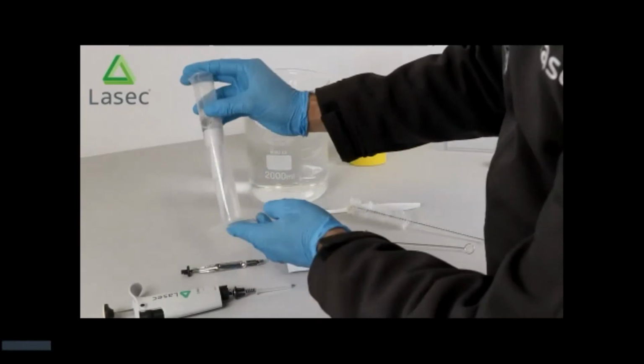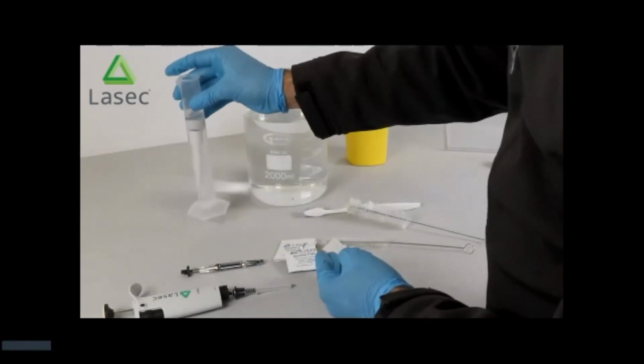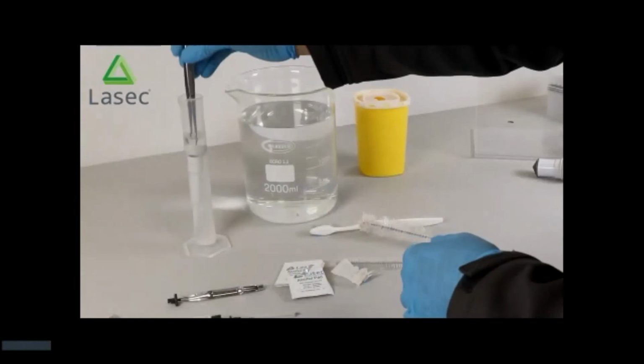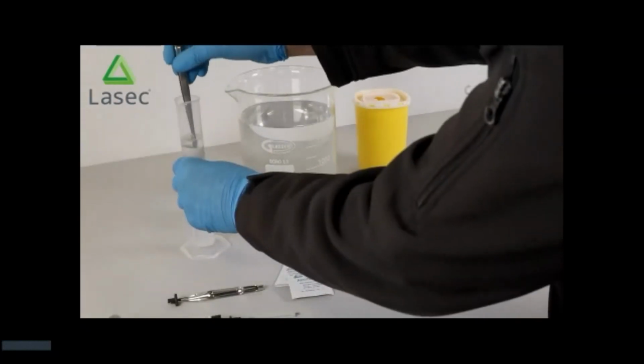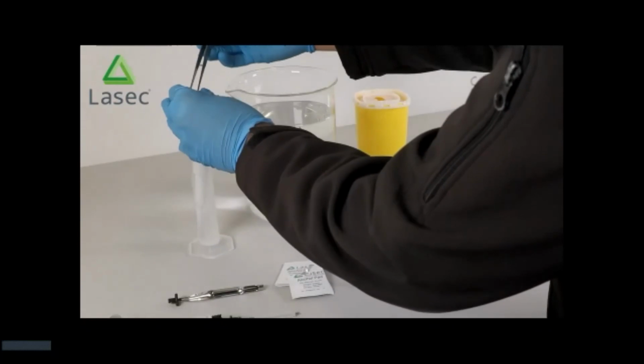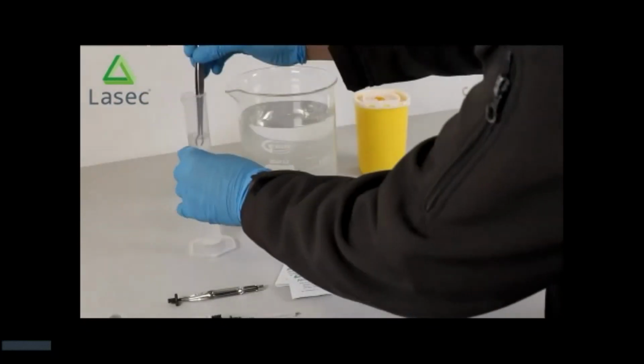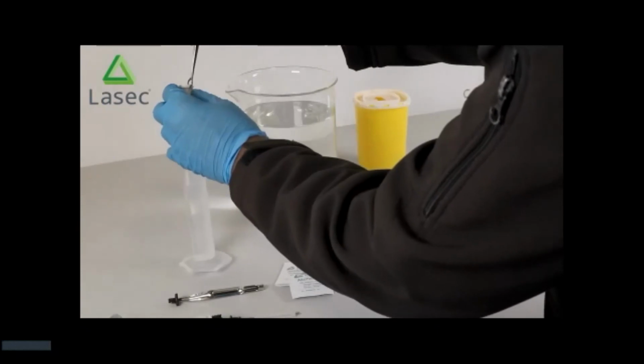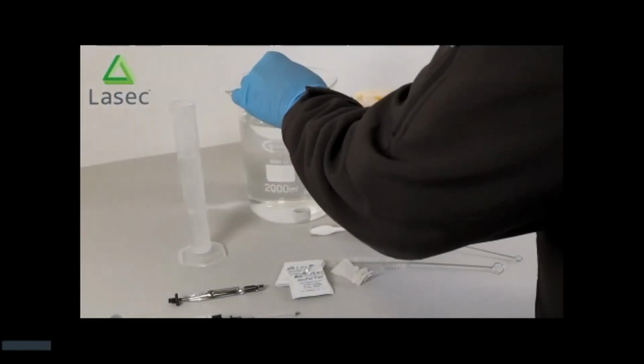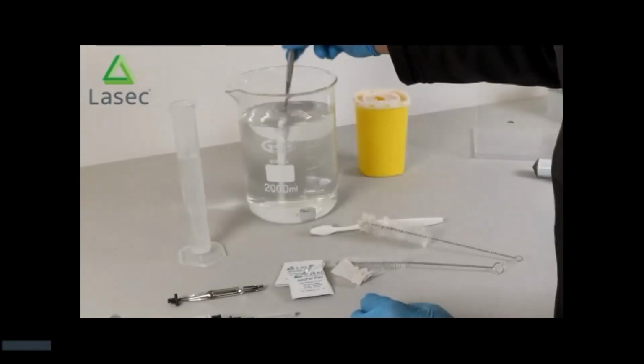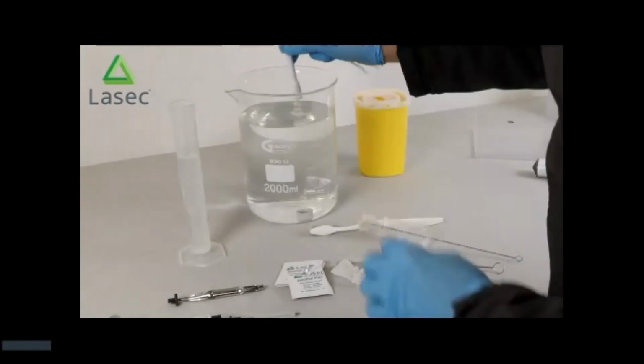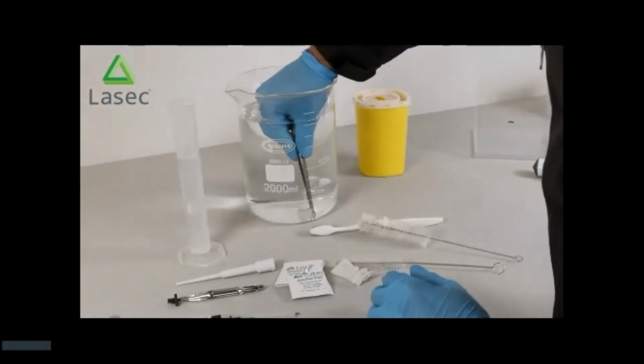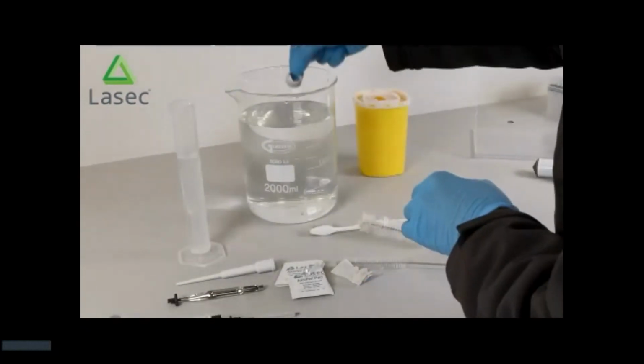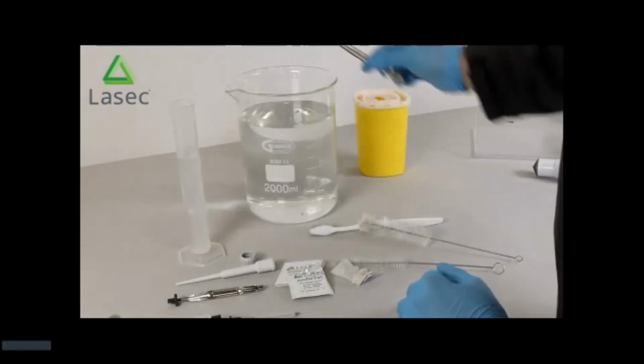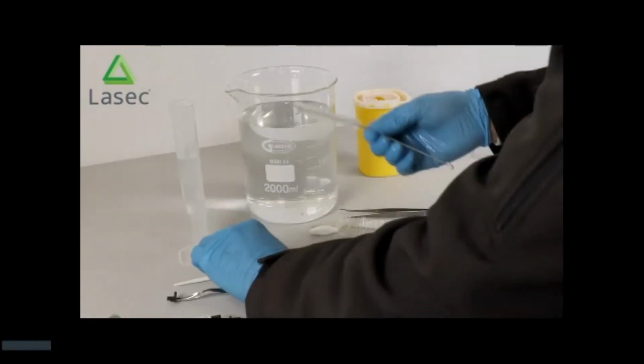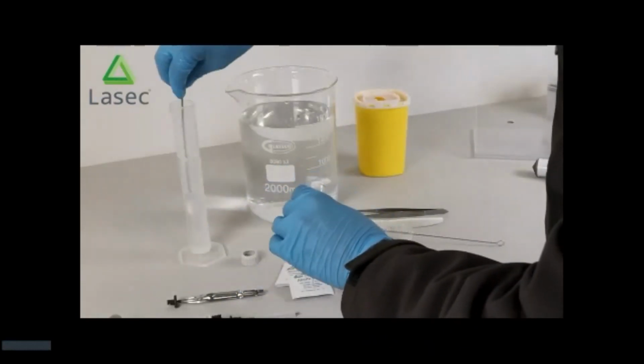Should you have anything in your tip holder that you want to remove or dislodge, you can completely submerge these parts in an ethanol solution and mechanically shake that up a bit to dislodge any particles that might be in that tip holder. It is incredibly important that after dousing or wiping off or leaving the parts in the ethanol, you thoroughly rinse it with distilled or deionized water. So water that we know does not have any particles or pollutants or contaminants in it, and that we let the parts sufficiently dry before we reassemble them.